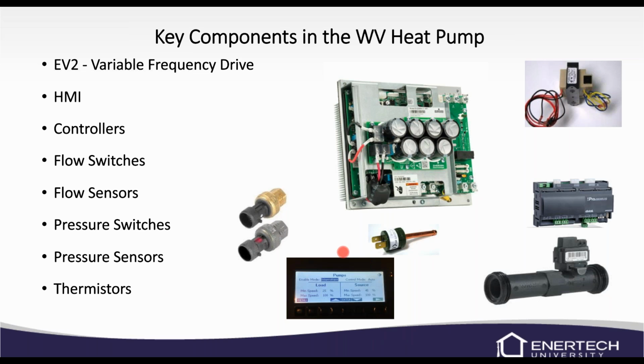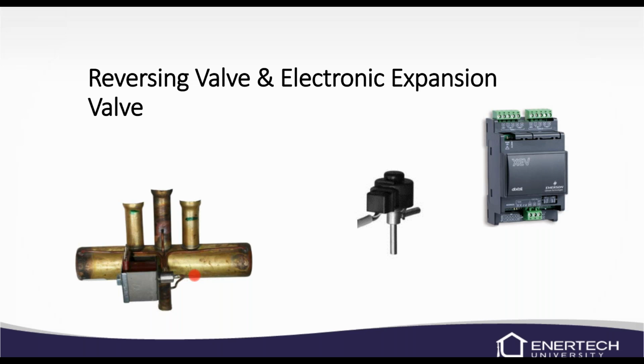Now, all of these would be for reference. If we were diagnosing, we'd always want to confirm that your flow sensor is reading properly, that your pressure switch is working properly. So we'd always want to confirm whenever we're diagnosing with our standard diagnosing tools, but this makes it helpful with the HMI. We can quickly look and see what's going on with the system. We do have a terminal strip that is removable. So if you want to jumper the unit and get it to run, you can remove the terminal strip and just jumper out the unit. We'll talk about that terminal strip in just a few more minutes.